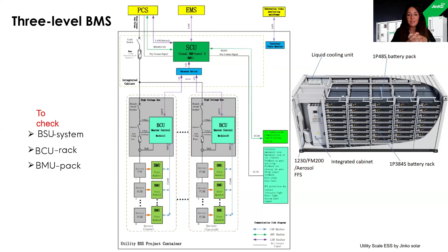So the three levels, as I commented: the first one is the BMU for every single pack. The second level is the BCU, in the middle of the picture, every single rack has a second level of BMS, connected to level 1 and to the third level, the SCU, which collects or gathers data from the whole system. This third level is connected to the EMS and the PCS, which I would say are the key elements for controlling the performance of the battery, because the battery itself is just chemistry. So we need these devices to control the temperature and the performance of the battery.